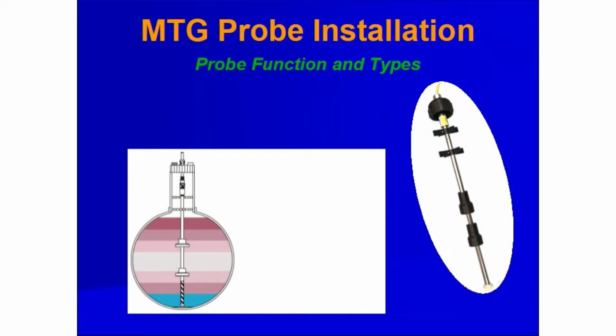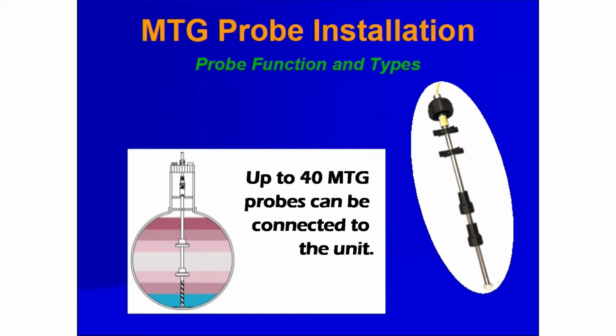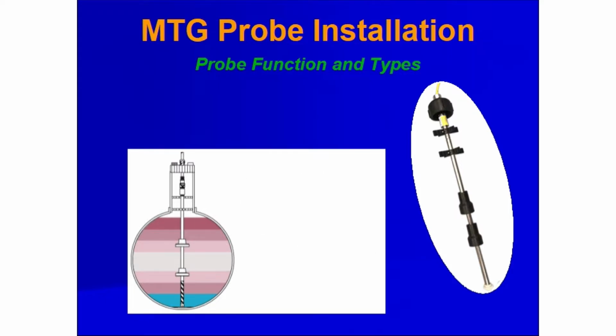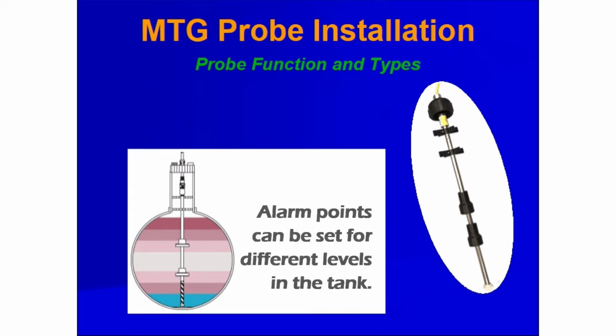Now, let's look at probe installation. Based on the configuration of the Proteus controller, up to 40 MTG probes can be connected to the unit. OMNTEC probes provide tank inventory data by monitoring product, water, and temperature levels. Alarm points can be programmed for different levels in the tank.